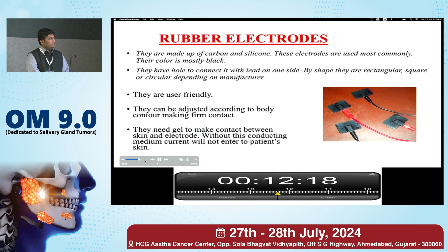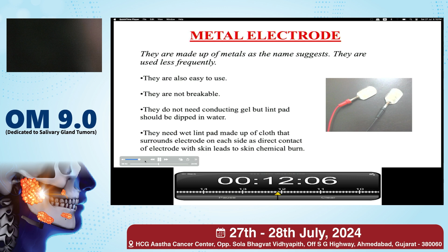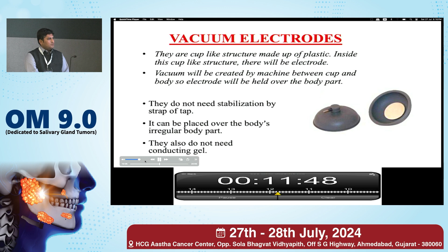Metal electrodes. Metal electrodes do not need conducting gel, but lint pad should be dipped in water. They might lead to skin chemical burns occasionally due to metal coming in direct contact with the skin under electric activity. Vacuum electrodes. These do not need stabilization by strap or tape. It can be placed over the body's irregular parts. They also do not need any conducting gel.